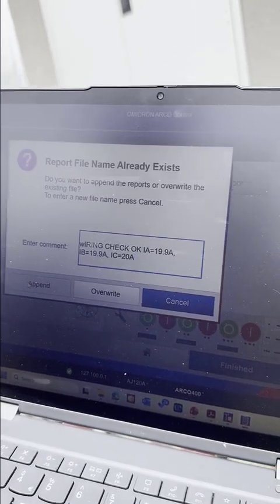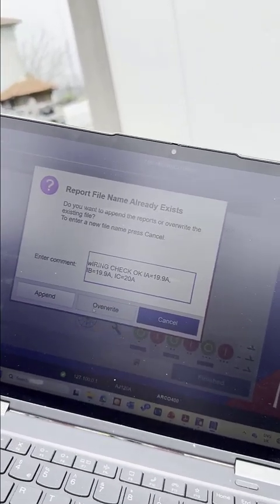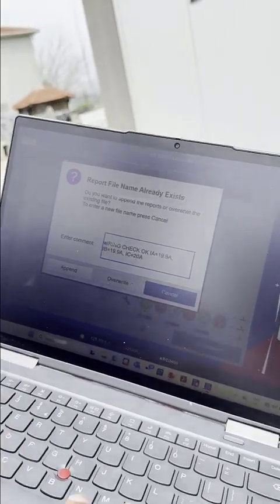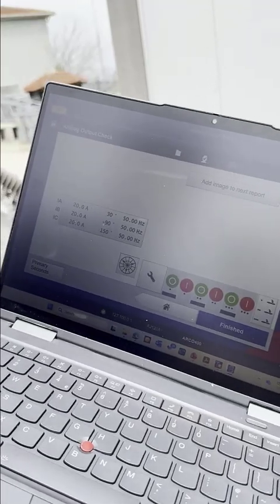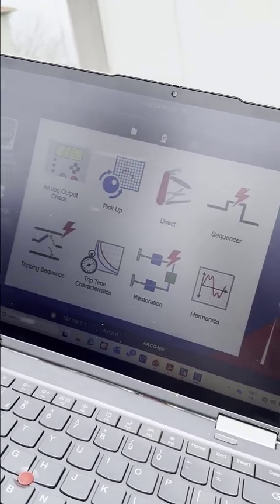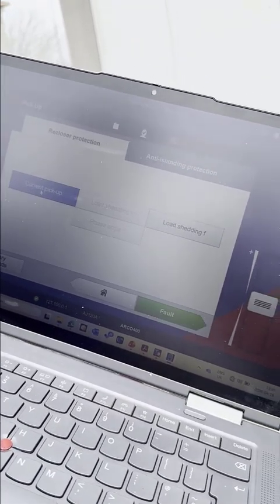Then you can append if you need to insert this to be a new test report, or you can overwrite if you have an old one which is wrong, and you can override this one to the old one, so you will have the last saved ones. So now I will click append, then I will click finish. Now the second one is the pickup. We can select now the current pickup to check the pickup and the drop off for different fault loops.